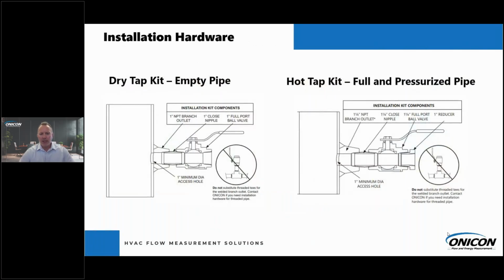As well as when you order our meters, you can actually purchase the installation kit through ONICON when you place the order. We have two different versions of dry tap kit, so those are great for new build, new construction. It comes with a 1-inch ball valve, so our meter is readily available to thread in, and you're good to go once you put it to the insertion depth. What's great about it is once you've commissioned it, and later down the road, if you need to remove that and send it back for recalibration or anything, you have that ball valve there. You can easily remove it, close the ball valve, unthread it, and you're ready to send it back to ONICON.